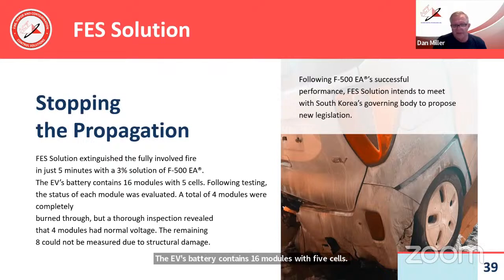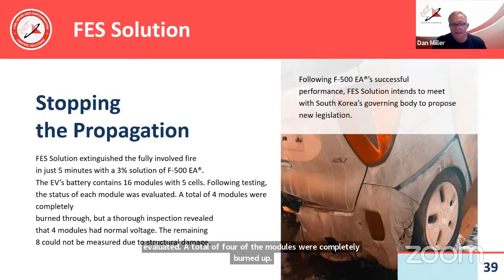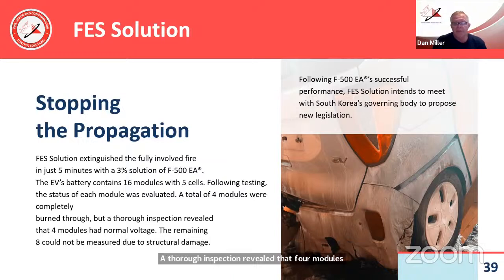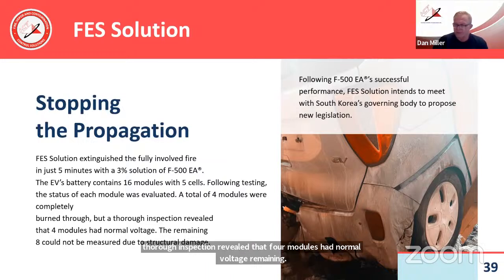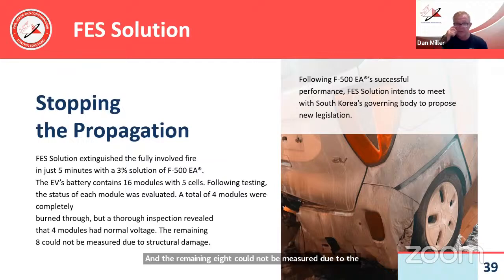Following the testing, the status of each module was evaluated. A total of 4 modules were completely burned up. A thorough inspection revealed that 4 modules had normal voltage remaining, and the remaining 8 could not be measured due to structural damage of the modules themselves. Not uncommon.